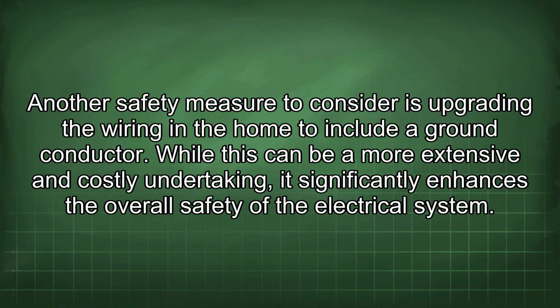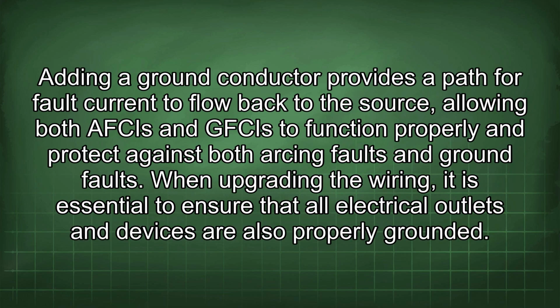Another safety measure to consider is upgrading the wiring in the home to include a ground conductor. While this can be a more extensive and costly undertaking, it significantly enhances the overall safety of the electrical system. Adding a ground conductor provides a path for fault current to flow back to the source, allowing both AFCIs and GFCIs to function properly and protect against both arcing faults and ground faults.